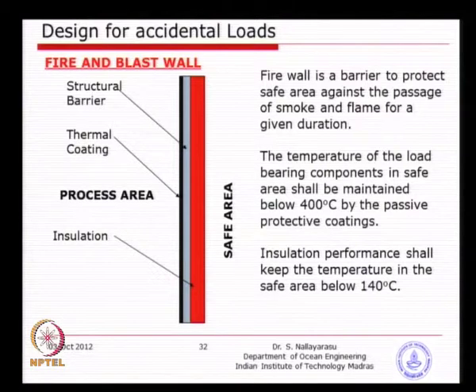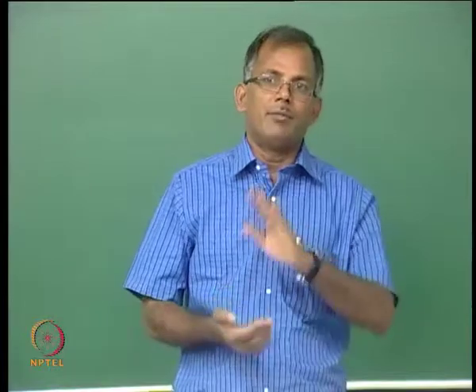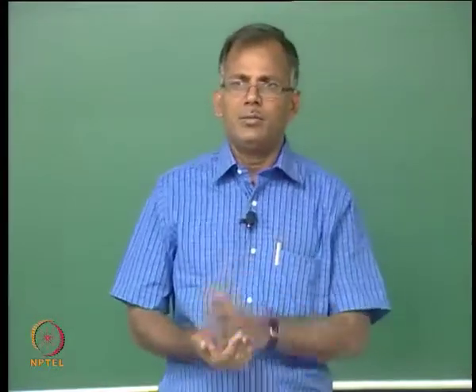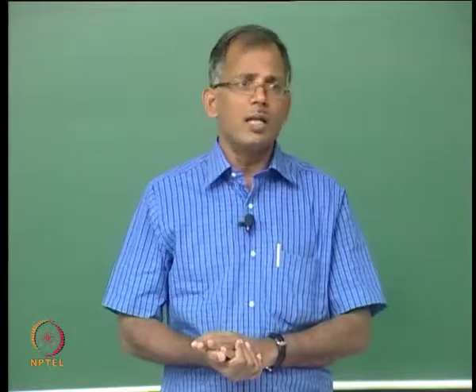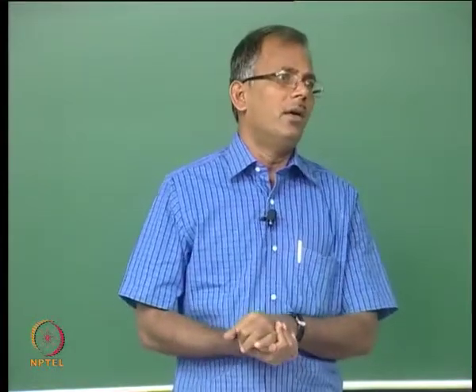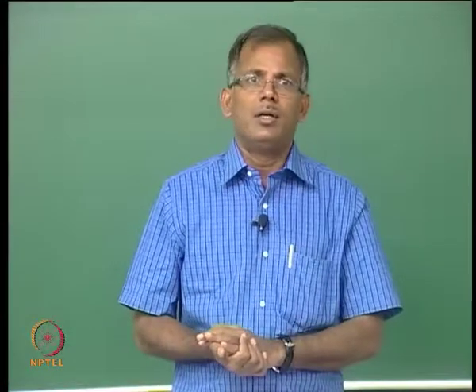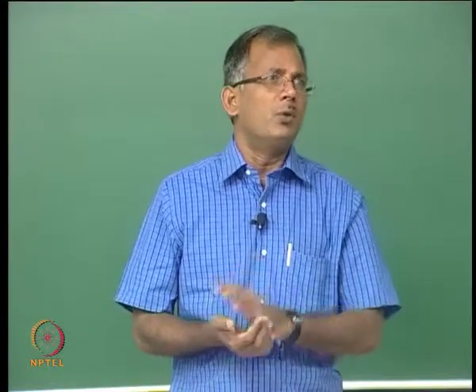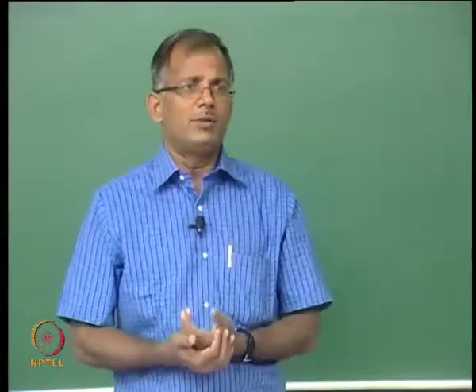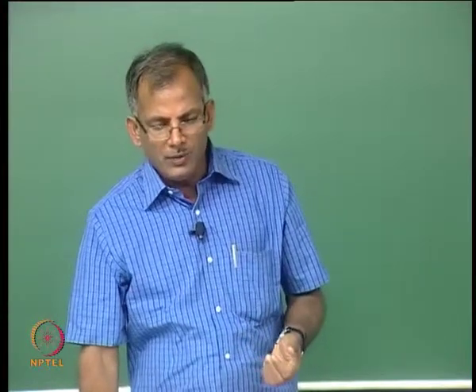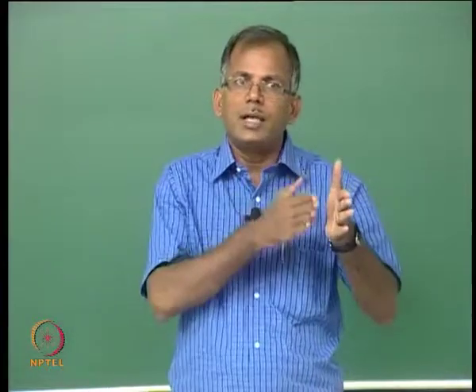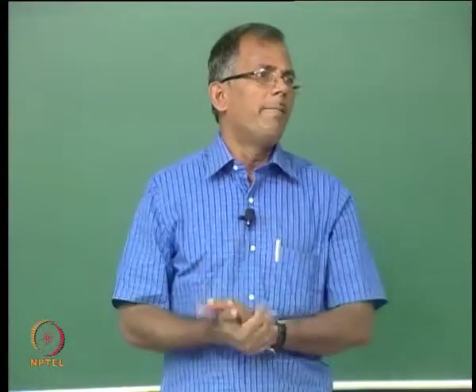There are several materials for insulators. Steel is a very good conductor of heat, so we need exactly the opposite. Most of the time wool is used, and glass wool is the best material nowadays — used in most air-conditioned spaces. Glass wool is preferred and easily available. The larger the thickness of the glass wool, the higher the reduction in temperature. Typically 30 mm, 50 mm, or 100 mm are used.